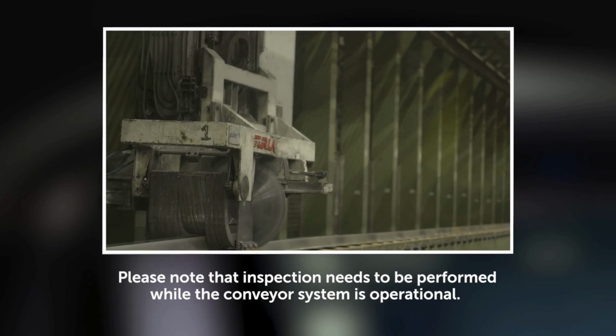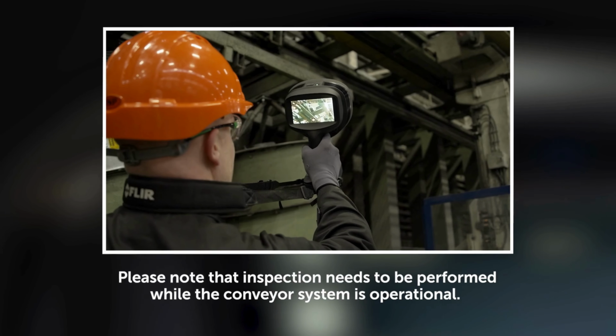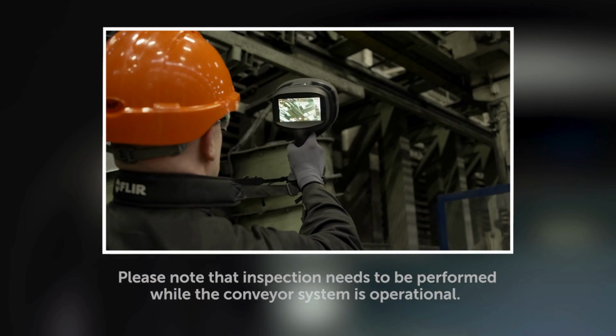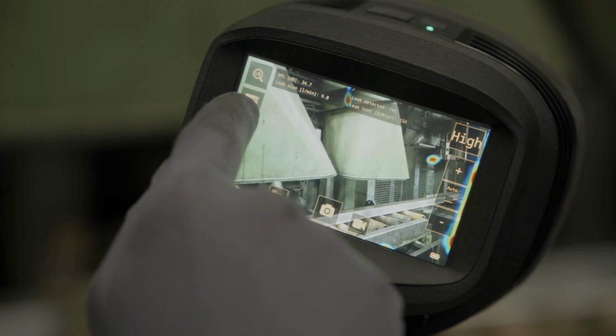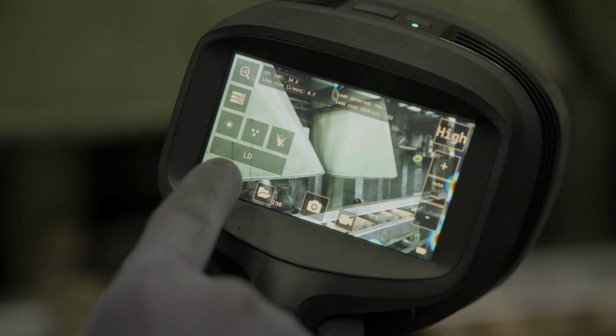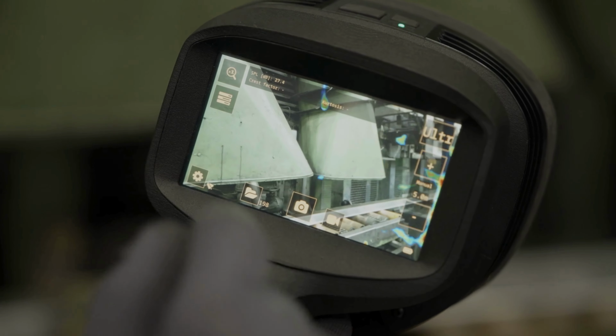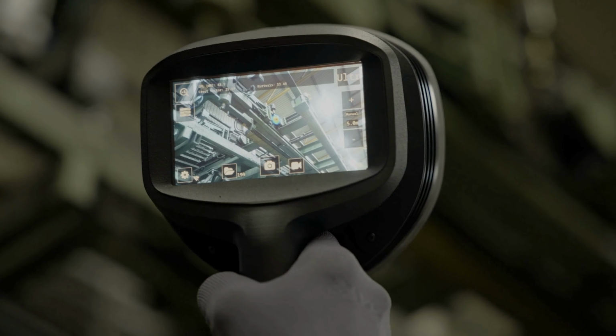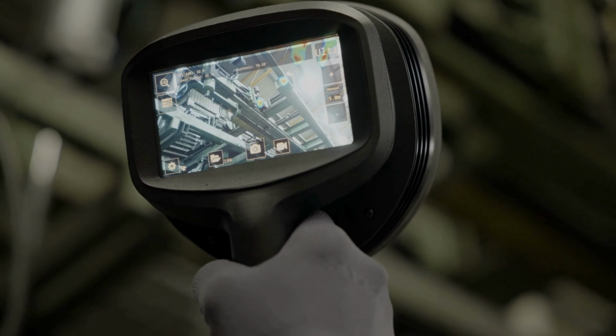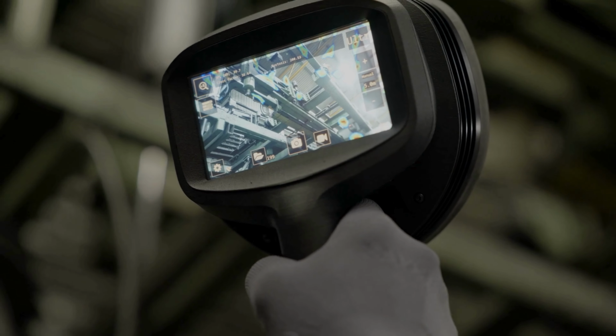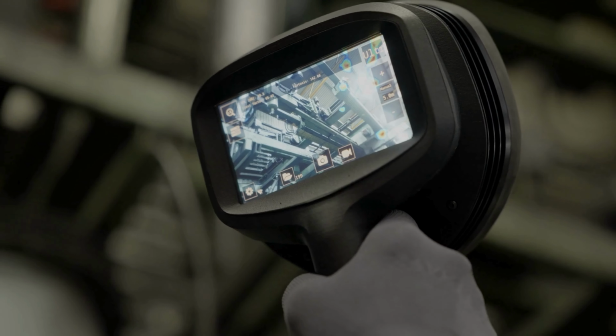Bearings that are in need of lubrication or are developing faults begin to emit excessive noise. The mechanical mode on the Si2 provides three metrics: SPL, crest factor, and kurtosis. The Si2 will automatically show bearings that emit more noise than other bearings in the vicinity. This makes it easier to identify the bearings that are likely to be in bad condition.